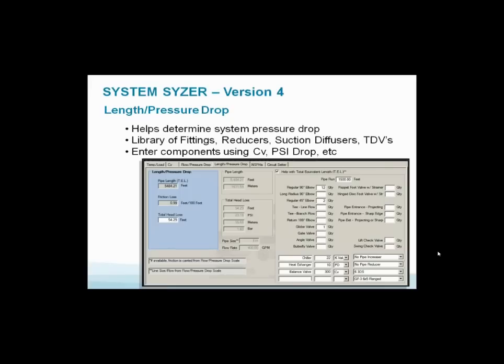How about length and pressure drop scales? How do we come up with a total pump head we need using the System Syzer? Look at this chart on version four of the Windows version that you can download from our website - it's free, no cost. Every engineer, every designer picking pumps needs this because it's becoming code. Before we go to the code piece, let's look at this. This is a selection chart. You already selected the GPM, you already picked your pipe size. Now what? Now we've got to come up with a total pump head required from a pump.